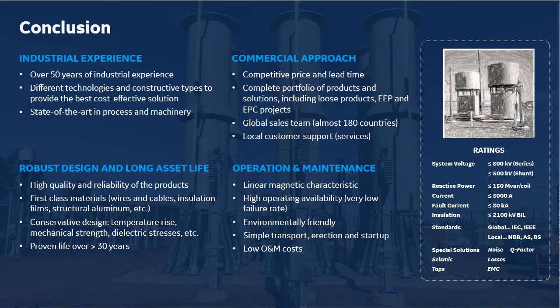Just let us provide you what the natural Q factor is, but we need to remember, Q factor is related to the losses. It's basically the power divided by the losses of the reactor. So if you specify a Q factor that is very high, it means that we will be forced to use flat transposed cable technology, low loss, and we may also need to keep the reactors very cold to meet the Q factor requirement. So if you're sure about the Q factor, feel free to specify. If you're unsure, just let us specify it for you. And again, if it's related to losses, just provide us the dollar per kilowatt, and we will bring the best, most competitive design to you.